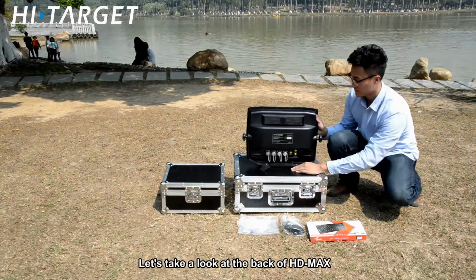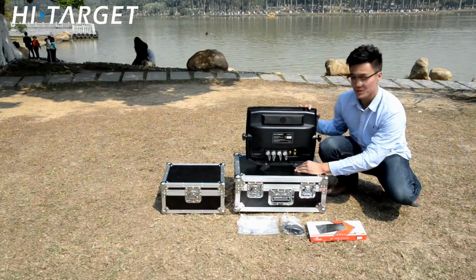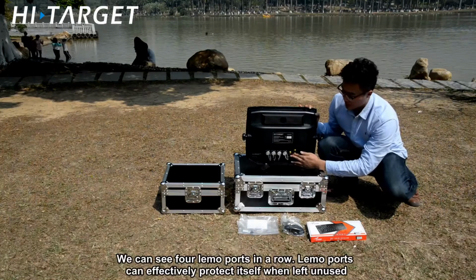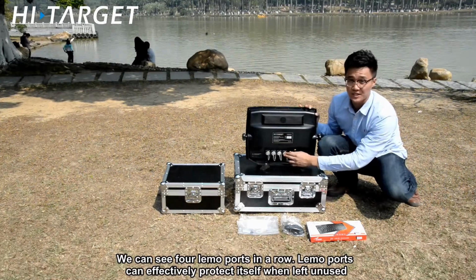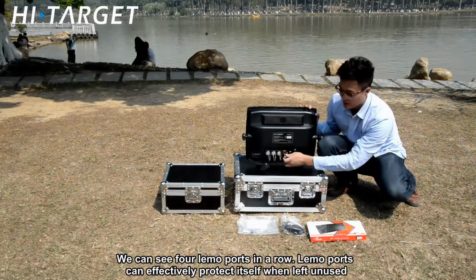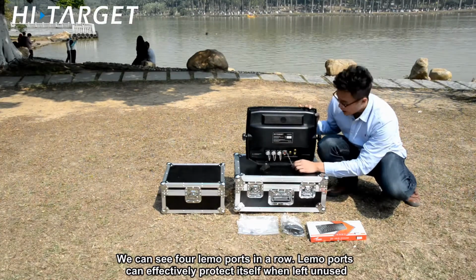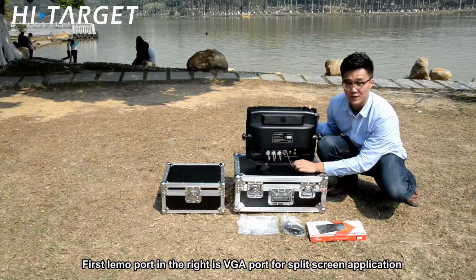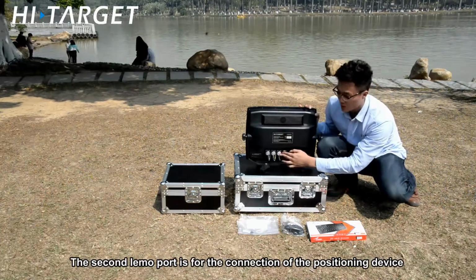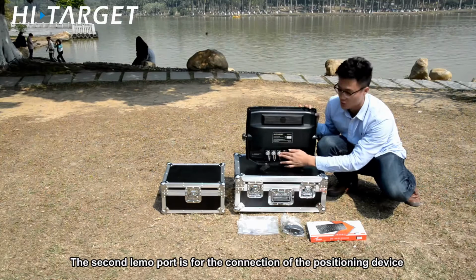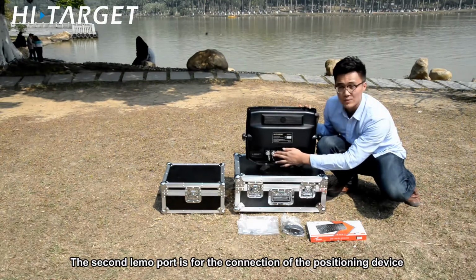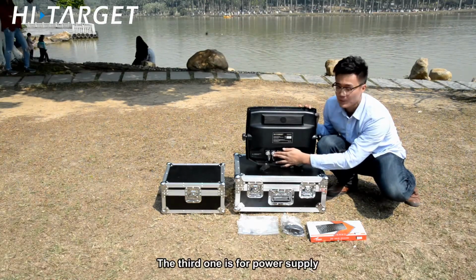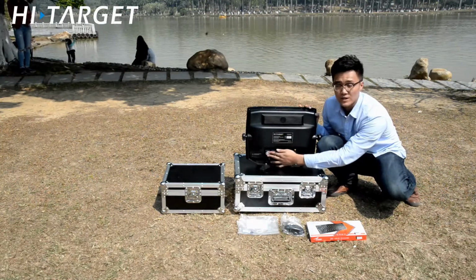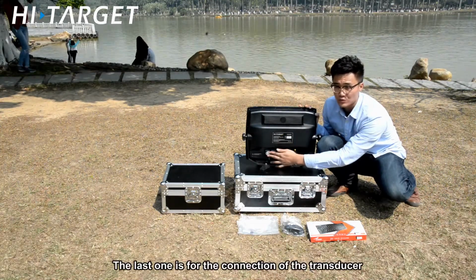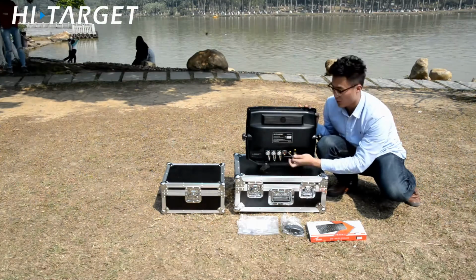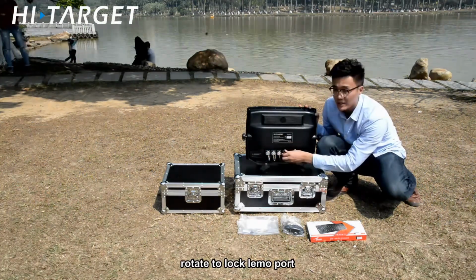Let's take a look at the back of HDMax. We can see 4 LEMO ports in a row. LEMO ports can effectively protect themselves when left unused. The first LEMO port on the right is the VGA port for split screen application. The second LEMO port is for the connection of a position device. The third one is for power supply. The last one is for the connection of the transducer. Rotate to lock the LEMO port.